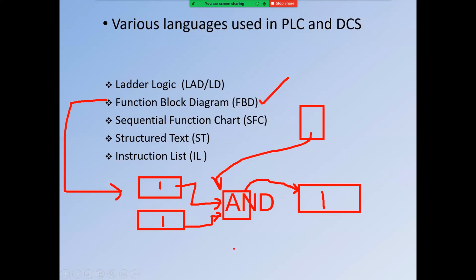But remember this isn't as simple as it looks, because we have to handle multiple input conditions for one AND block — for example, if this is on and that is off for 5 seconds, then it will set and turn on the output. There can be 5 to 10 conditions for one application, so it requires logic understanding to develop this logic and download the program into the DCS.